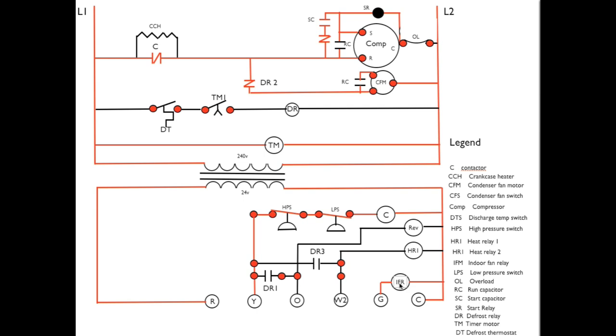Power will flow from R to Y, then pass through the normally closed high pressure switch and low pressure switch to energize the C contactor.